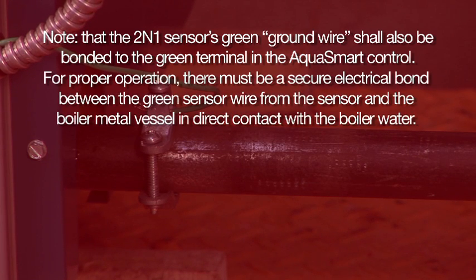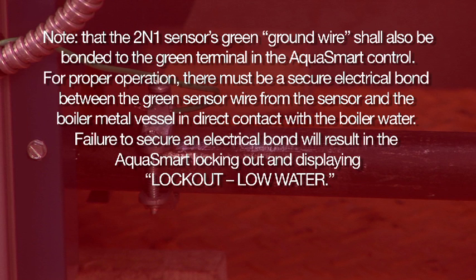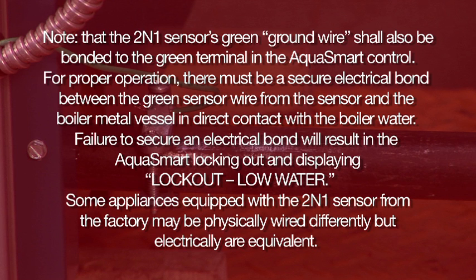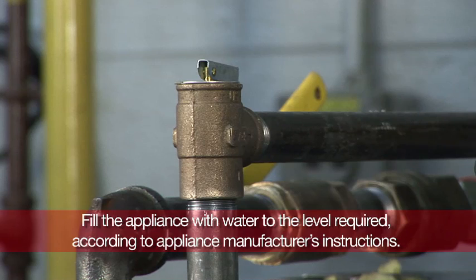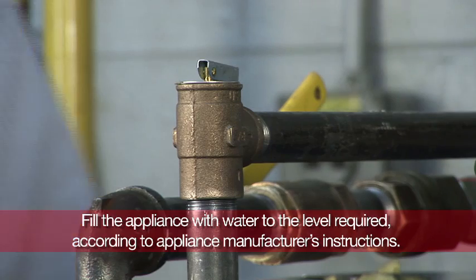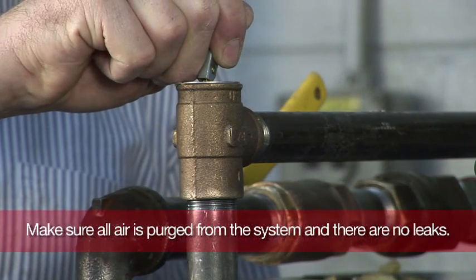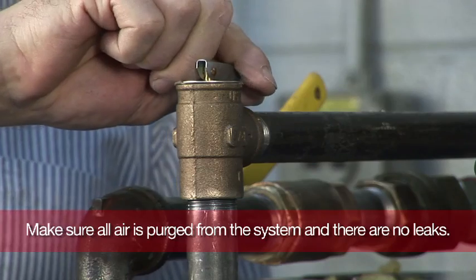For proper operation, there must be a secure electrical bond between the green sensor wire from the sensor and the boiler metal vessel in direct contact with the boiler water. Failure to secure an electrical bond will result in the AquaSmart locking out and displaying lockout low water. Some appliances equipped with the 2-in-1 sensor from the factory may be physically wired differently, but electrically are equivalent. The final step is to fill the appliance with water to the level required according to the appliance manufacturer's instructions. Make sure all air is purged from the system and there are no leaks.